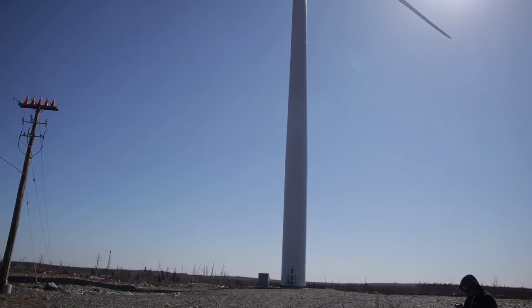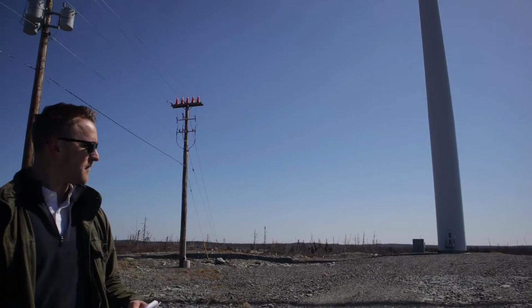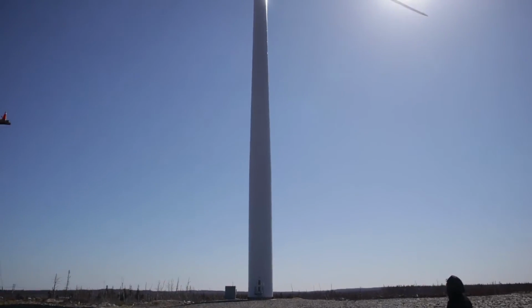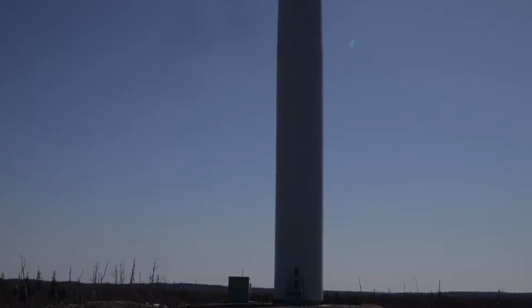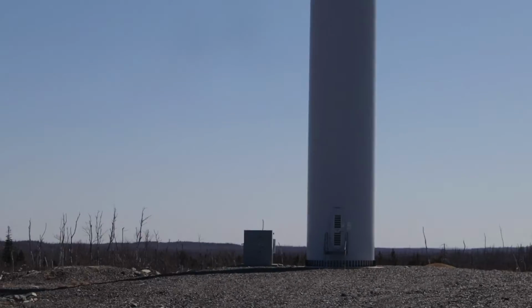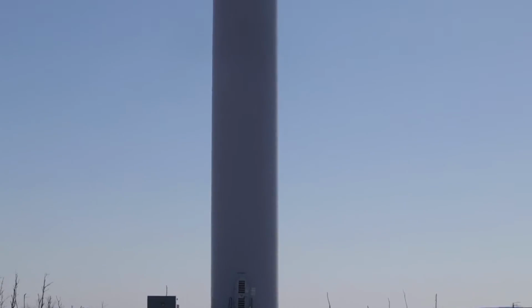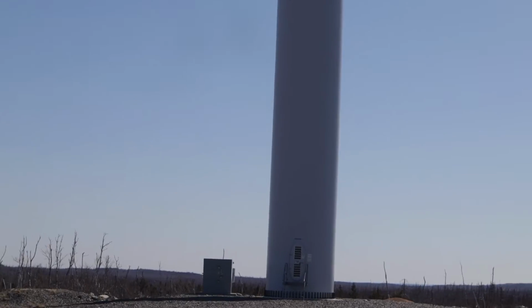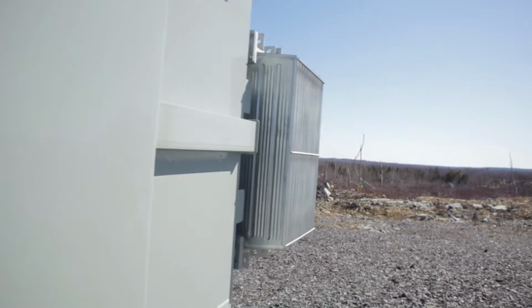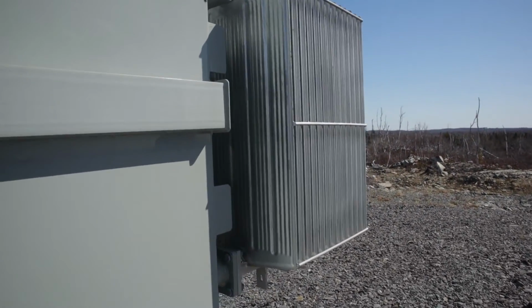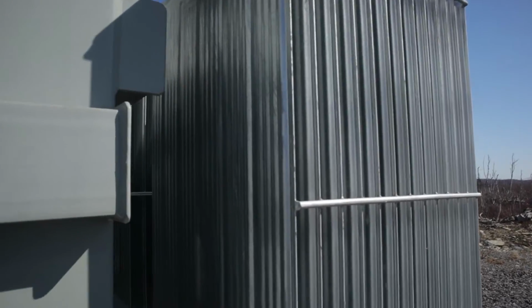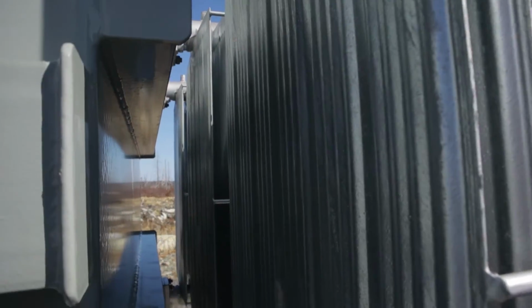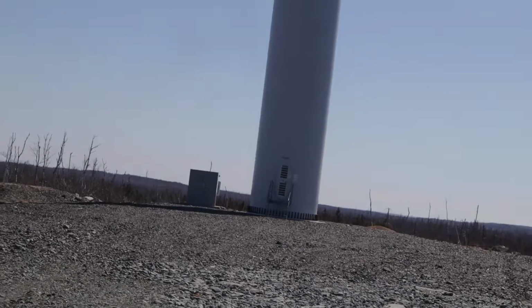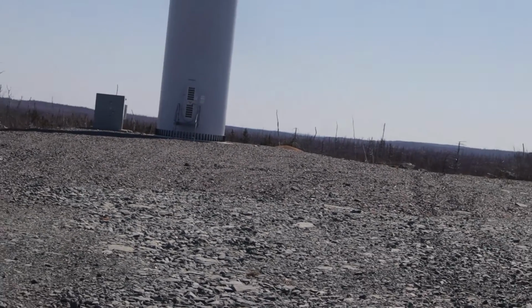Yeah, so then the final stage before we get to grid side power is the pad mount transformer. That's on the left hand side. It takes your 690 volts and steps it up to 12 kV. Is that a 1.6 megawatt transformer? Is that in the cabinet? It's 1850 kVA. Yeah, it's bigger. When you get over to it, it's a little bit bigger than it looks. But yeah, we're still 300 meters from the tower.